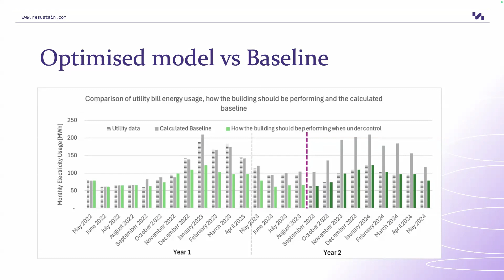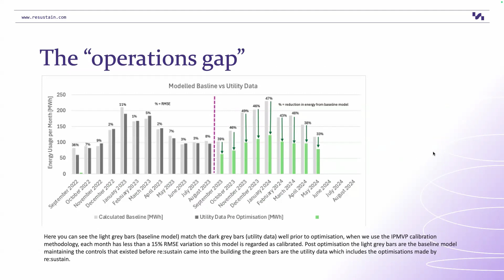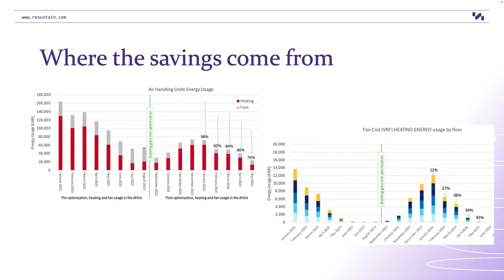So here you can see we're looking at 40 to 50% savings month on month through the control optimizations, and you can see those are from heating and fans - this is the air handling unit. You start seeing 56%, 60% savings, these huge drops in the central ventilation. The scales are incredibly different - 180,000 to 20,000. But you can start seeing how the VRF units are affected on each floor by the air handling unit being adjusted. In January we were about 14,000; by the next January, down to 12,000. They're starting to reduce the amount of heating they do as well.